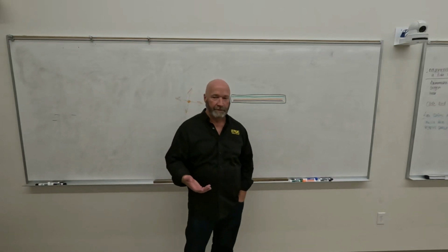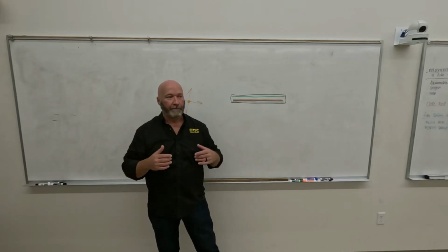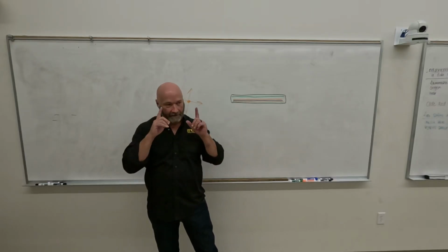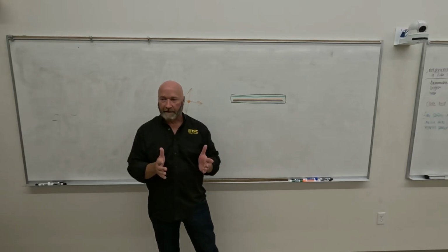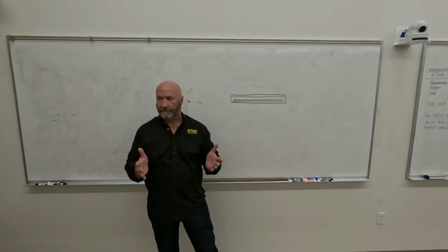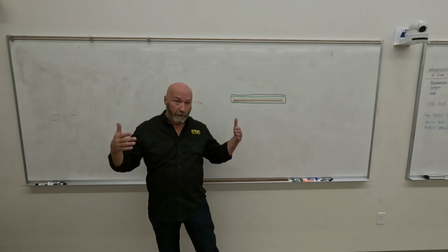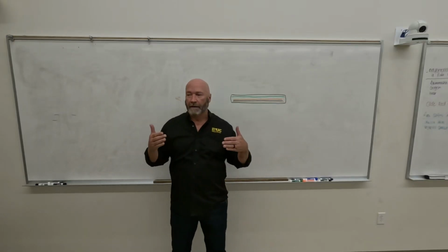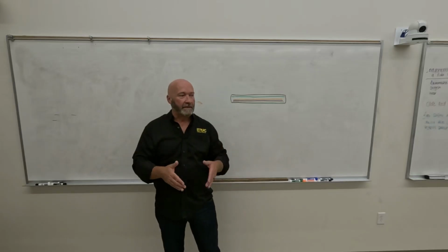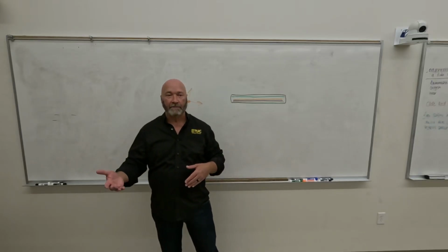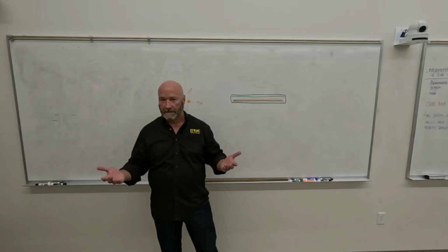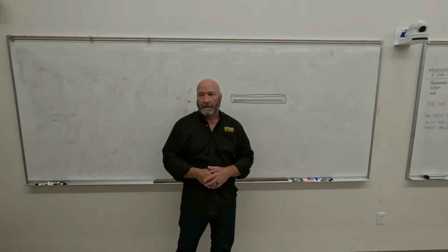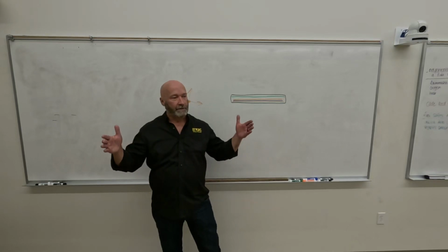Beam restriction, you'll hear it referred to as collimation. Collimation is blocking the beam. You're going to have a tendency to think of it as focusing the x-ray beam, but you don't. You can't focus x-rays. You can focus the stream of electrons, and we'll get there later in the semester, but you can't focus the x-ray beam. Once the x-ray beam is an x-ray beam, it is what it is. It's going to expose what you expose it to. So beam restriction is blocking.